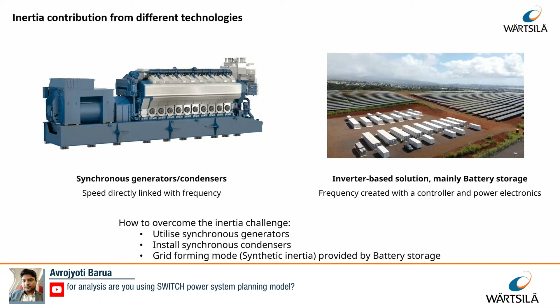When it comes to short circuit capacity, there's a big difference between synchronous generators and condensers and inverter-based solutions. With synchronous condensers, you have the capability to overload your generator for a very short moment. That's what short circuit capacity is about, being able to draw a lot of energy or power in a very short moment. Typical for these technologies, it's like 6 to 12 times the rated capacity, depending on the design. On the inverter-based solution, on the other hand, there are some challenges.